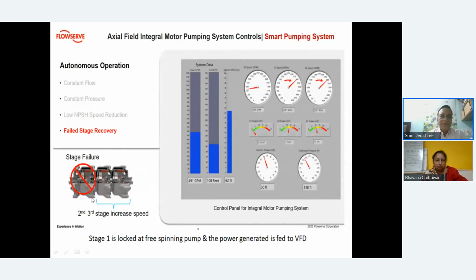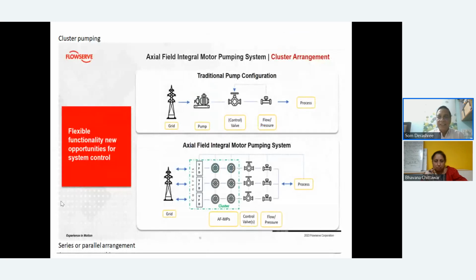Another advantage of this kind of system is that even if one pump has failed, it doesn't matter because it is all in line. So water will flow through. Maybe some pressure loss will happen here in an ideal situation, but then these two pumps will take over. Actually, the VFD will increase the speed so that you have the adequate head that was required and the flow that is required coming in, despite the fact that one stage is already down. So the typical configuration in future will be like this. Whether you need parallel or serial, this combination will be mounted as one in a setup, and whether you need more flow, more pressure, or less pressure, each stage will be combined like this, and all of them are operating through VFDs, each one of these, and they are a parallel system, and then it will go to the process. So this is a new emerging technology from Flowserve.